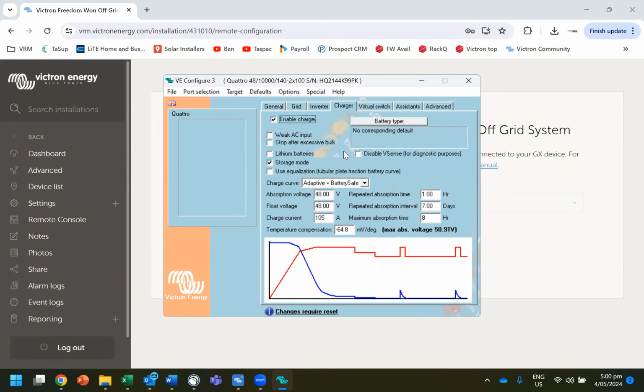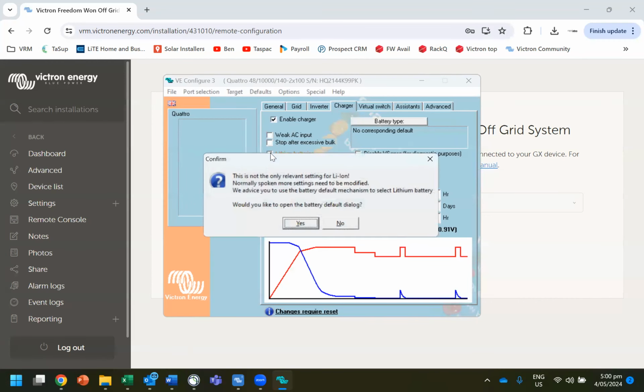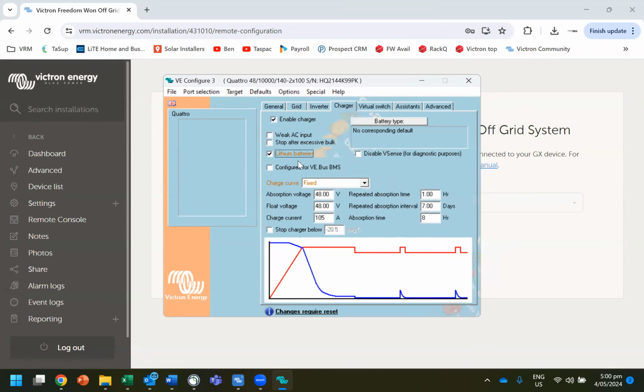Okay, so let's go to the charger mode. Now you're going to want to set up the battery for the correct charging. And for these voltages, you need to select lithium batteries. Don't open the battery dialog yet. You're going to select lithium batteries. Don't select configured for VE.Bus BMS, because that's only for Victron batteries. It's not for every other battery on the market, okay? If you do that, it's going to start doing some weird things and shutting down and doing random stuff.